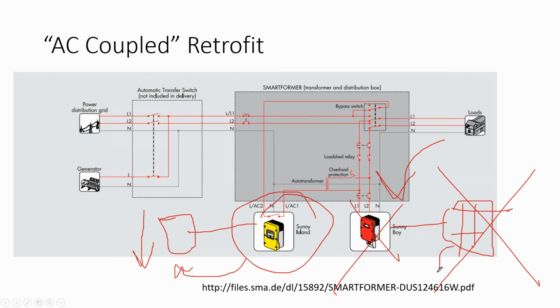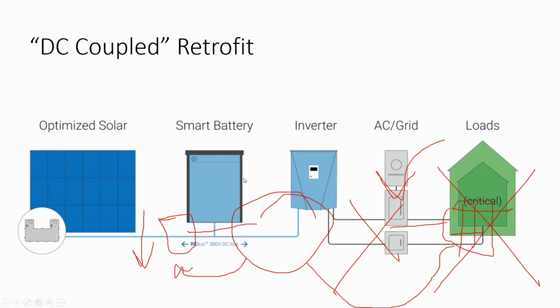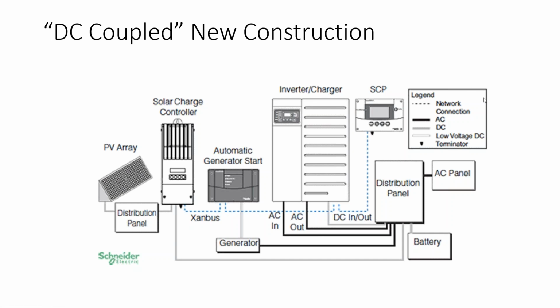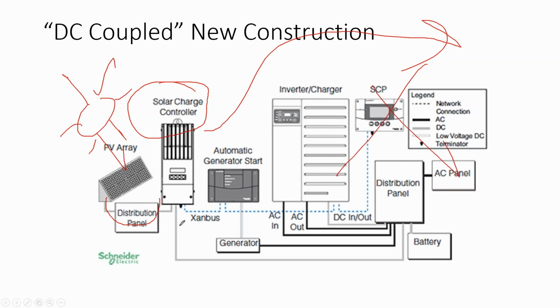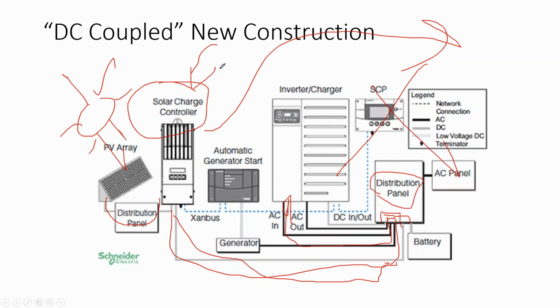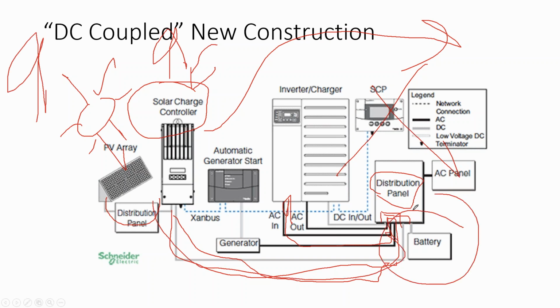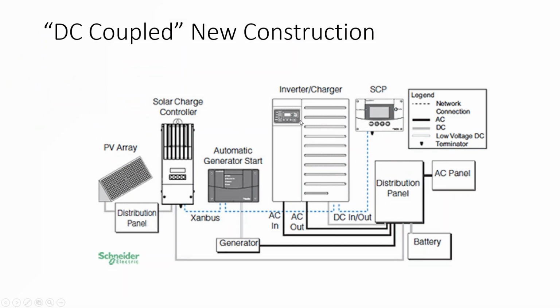So what you want is that direct drive of DC coupling between the solar array and the batteries, so that when the sun comes back up, your charge controller-which isn't connected to the grid or the AC side, it's completely isolated-can work. This distribution panel is a little misleading: there's a DC bus on it that gets wired into the battery, then into the DC side of the inverter. Because the charge controller isn't connected to the grid, it can turn on as soon as the sun comes up and charge the batteries back up so the inverter can turn on. DC coupling is the better solution for off-grid.